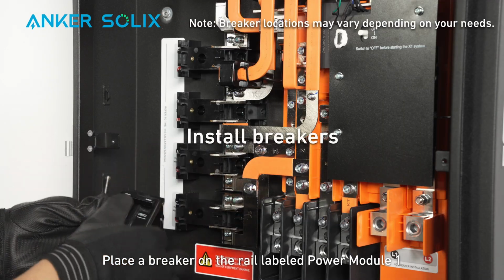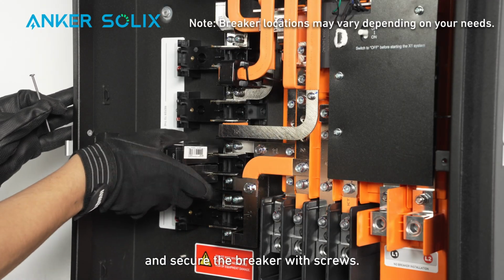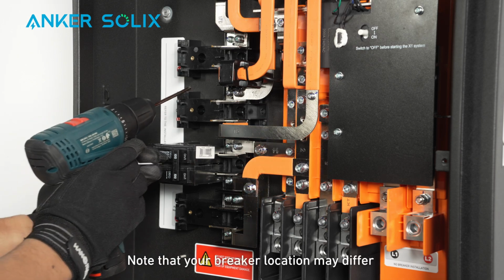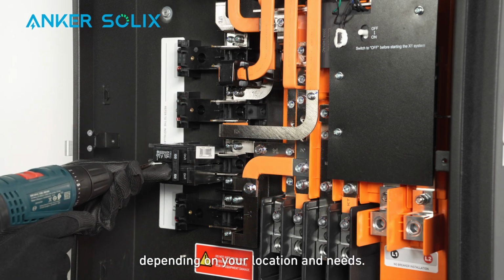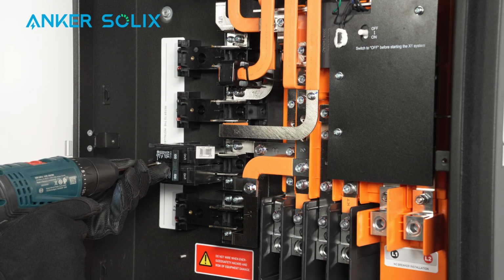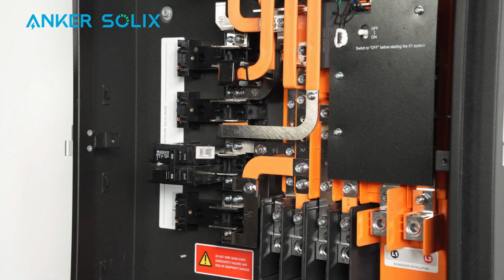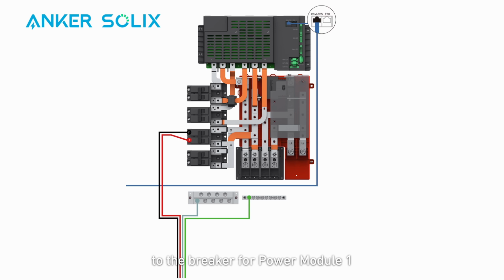Place a breaker on the rail labeled Power Module 1 and secure the breaker with screws. Note that your breaker location may differ depending on your location and needs. Connect the L1 and L2 cables to the breaker for Power Module 1.